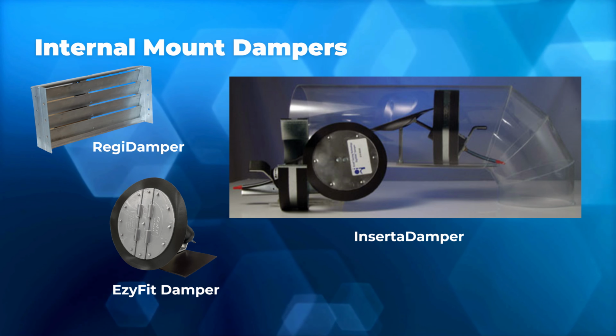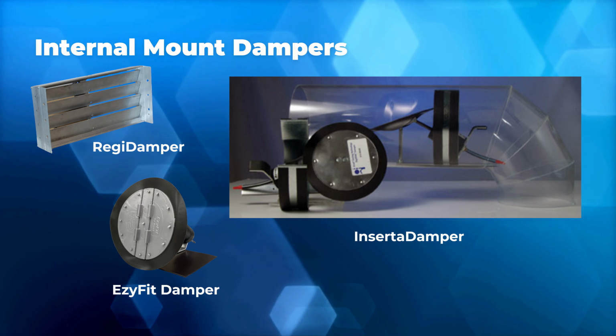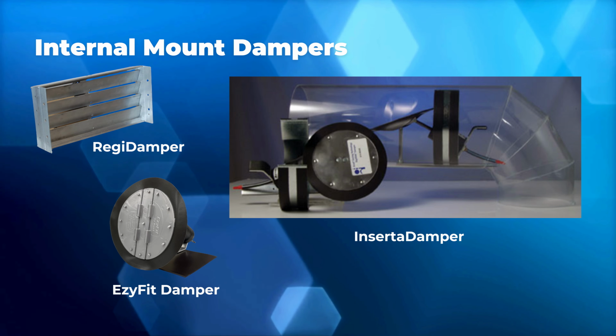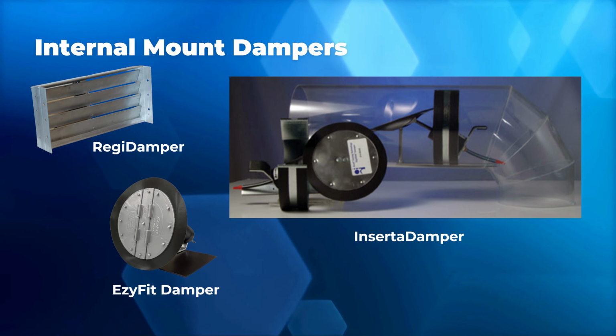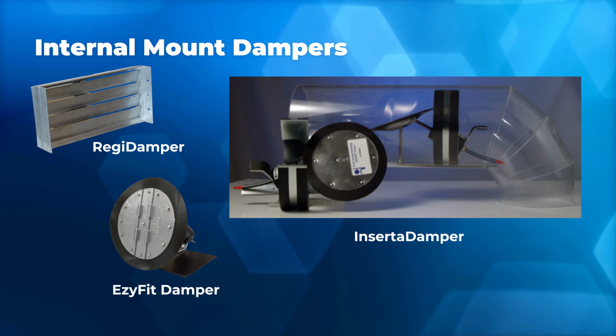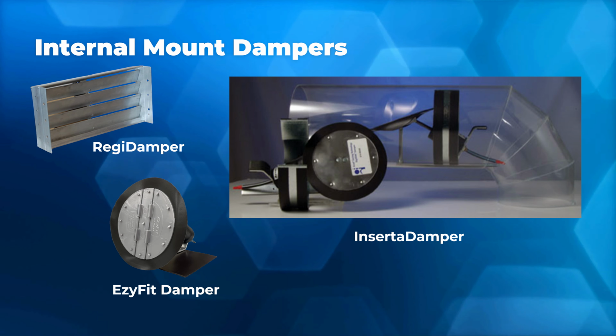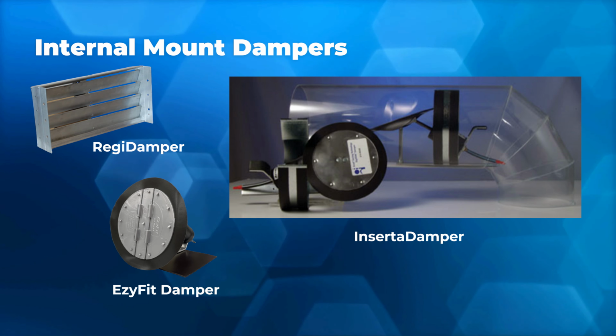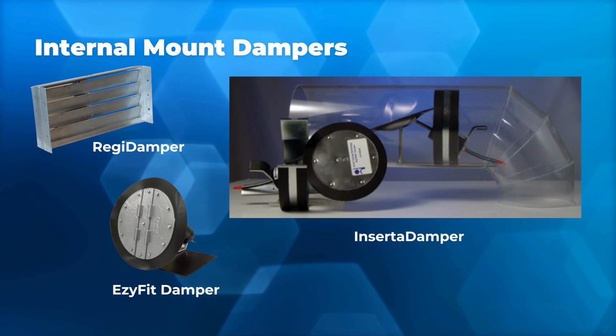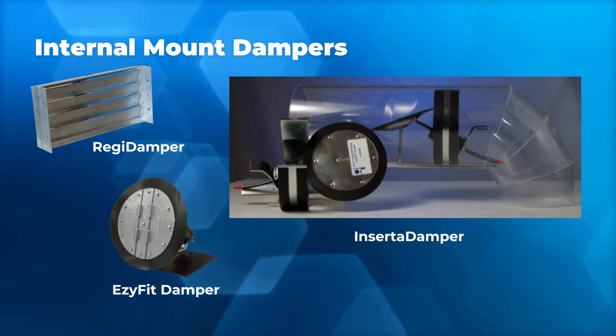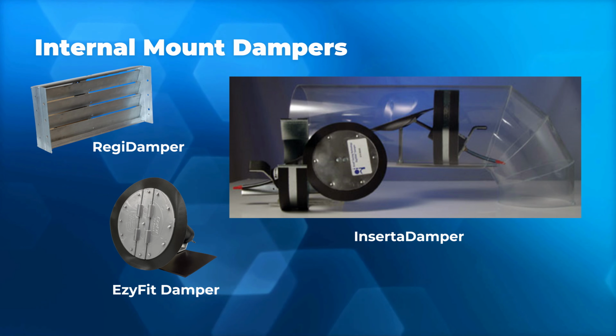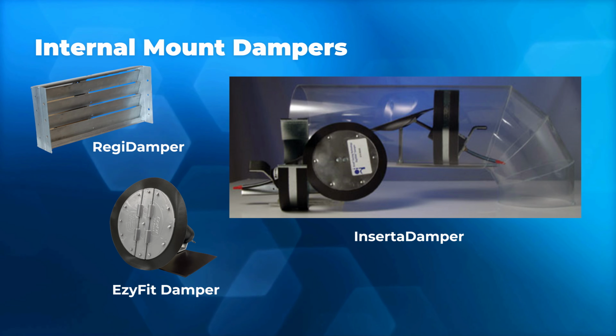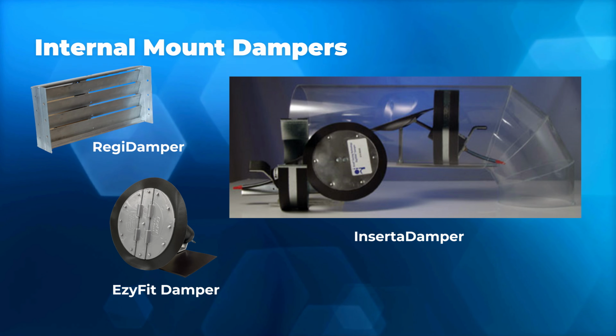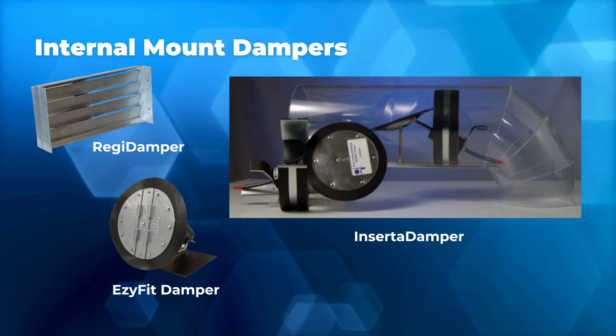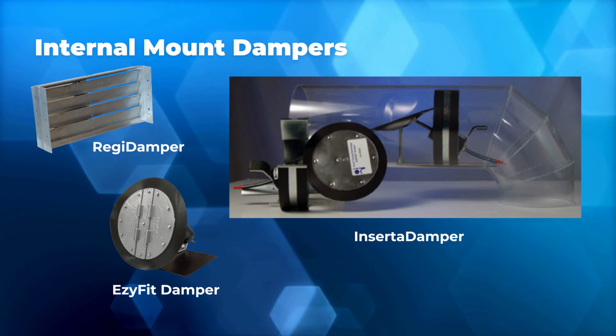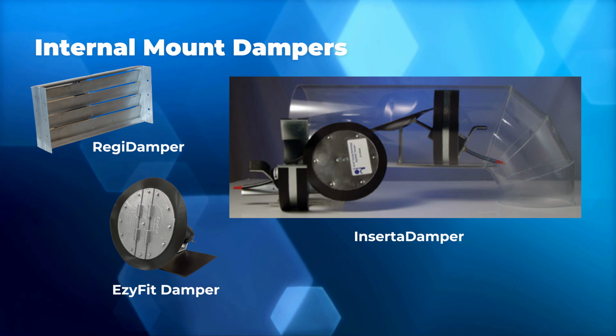Once you pull that back to your centralized location, then you could tie your tubing onto the string and then pull that through your ductwork up to where you have the damper itself. One thing to keep in mind when you're hooking up the tubing, you're going to want access to these dampers if there's ever a failure. So make yourself a service loop in the tubing itself. Just do a loop with the tubing and then feed that back through behind the damper itself. So if you ever have to pull the damper out, you're able to pull it out and not have to worry about damaging the damper or anything like that. It gives you plenty of slack to get to.